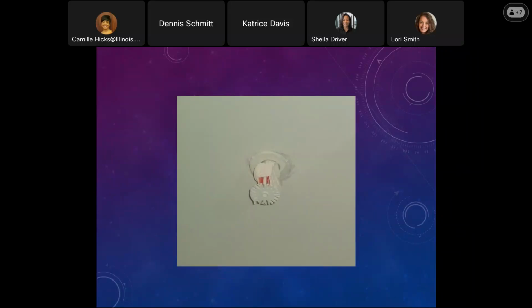This is another one, from a renovation project. The problem is they protected the glass vial with that orange device sprayed over it, but they didn't protect the deflector down below, the little prong thing. That deflector cannot be field painted, it has to be factory painted. So everything in this area, all these sprinkler heads, had to be replaced because sprinkler heads cannot be field painted.